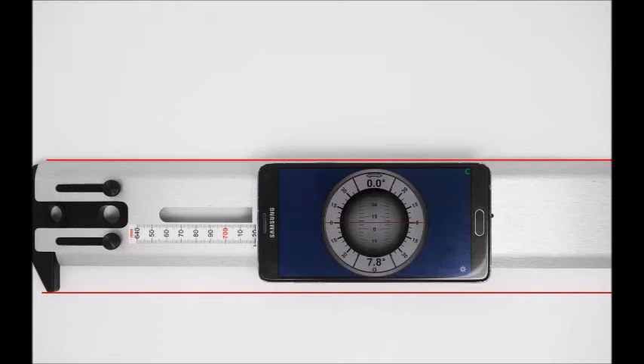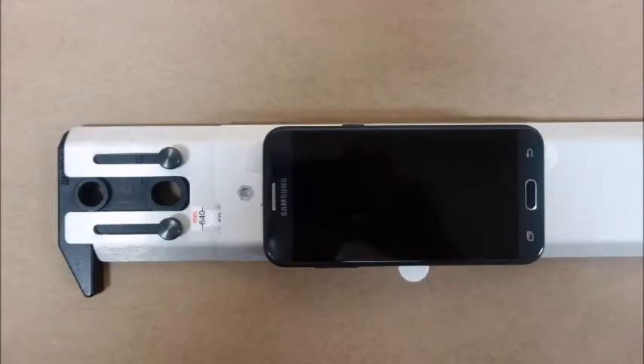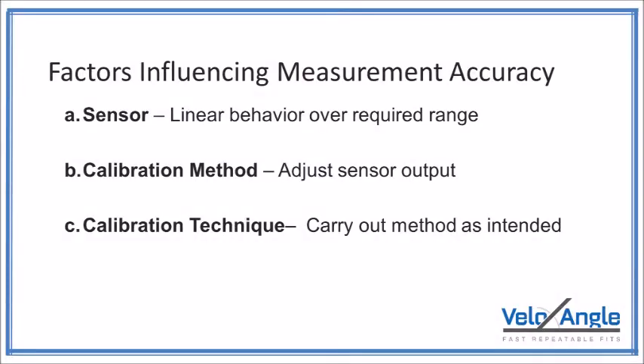Centering left to right on the screw holes used for the Pro inclinometer is a good reference location. If command strips are used, make certain the pull tabs don't extend past the top edge to ensure that they don't get pinched during calibration. We are now ready to discuss angle measurement. Broadly speaking, measurement accuracy can be broken into these 3 factors.